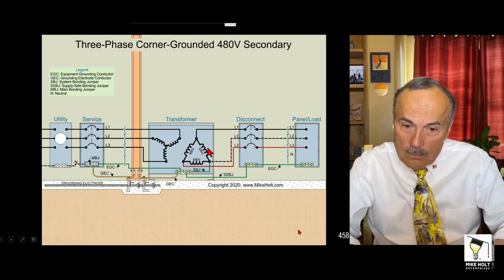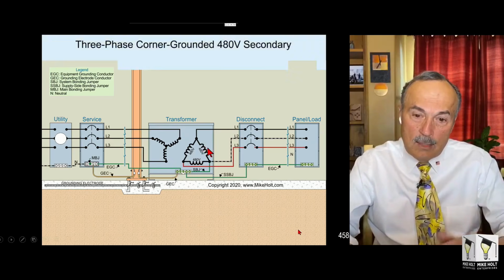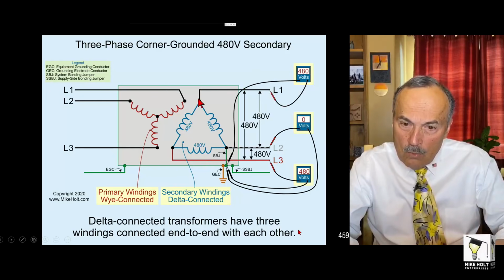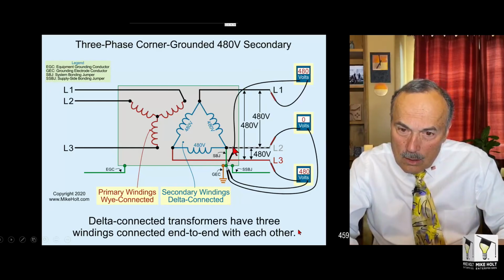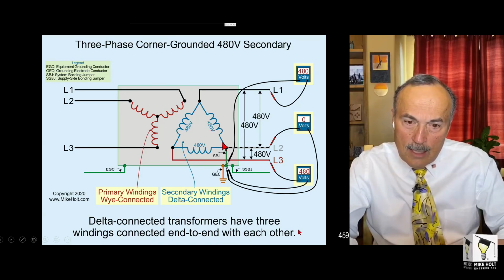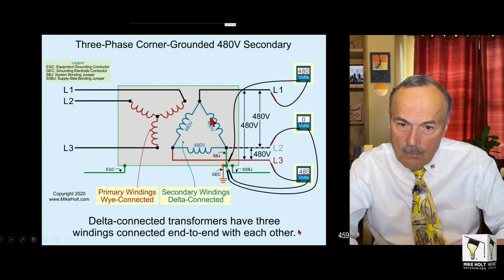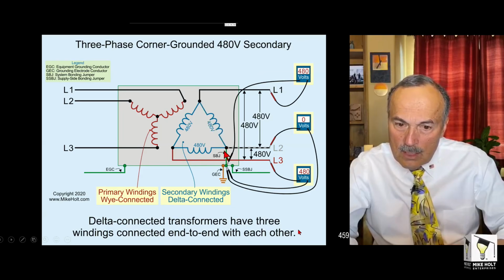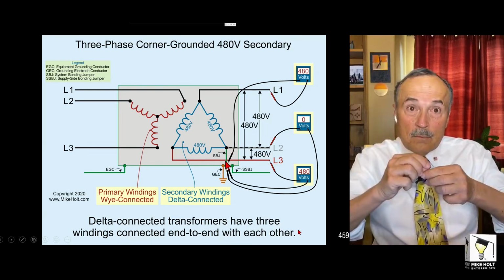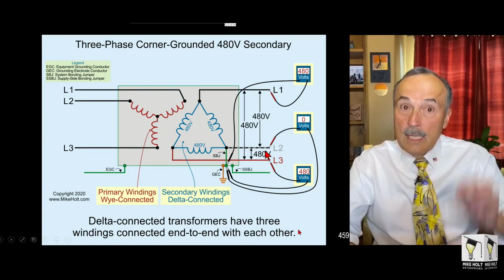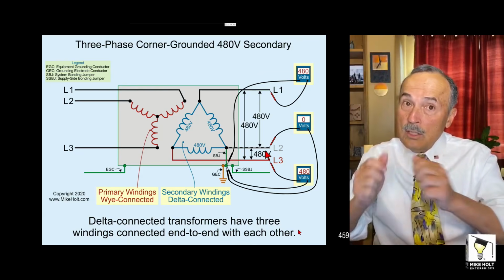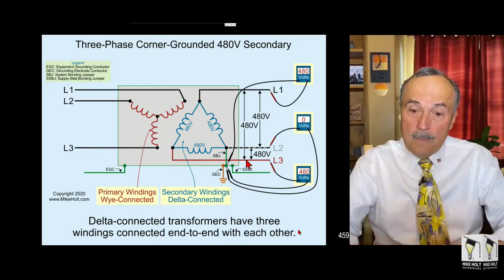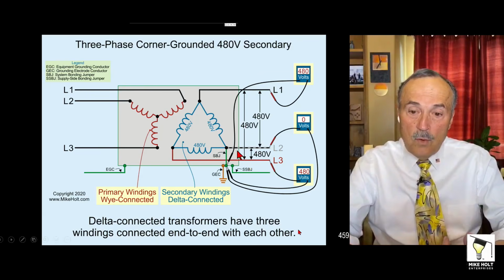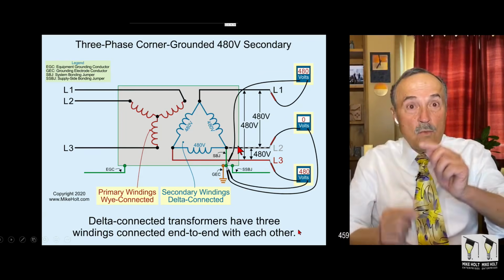Secondary is corner grounded. Okay, they're all 480 in this case here, which is correct. 480, 480, 480. Line 1 to ground is this winding here. I probably should mark them like A, B, C in the future maybe, that way I can see it. And that would be, let's say, that B phase right there, transformer. That's going to be 480. And then, of course, this is grounded at one point, which means this is called a grounded conductor, not a neutral conductor, because it's on the corner. It's not in the middle. That's 0. The other phase is 480, and voltage between phases is 480, 480, 480, 480.